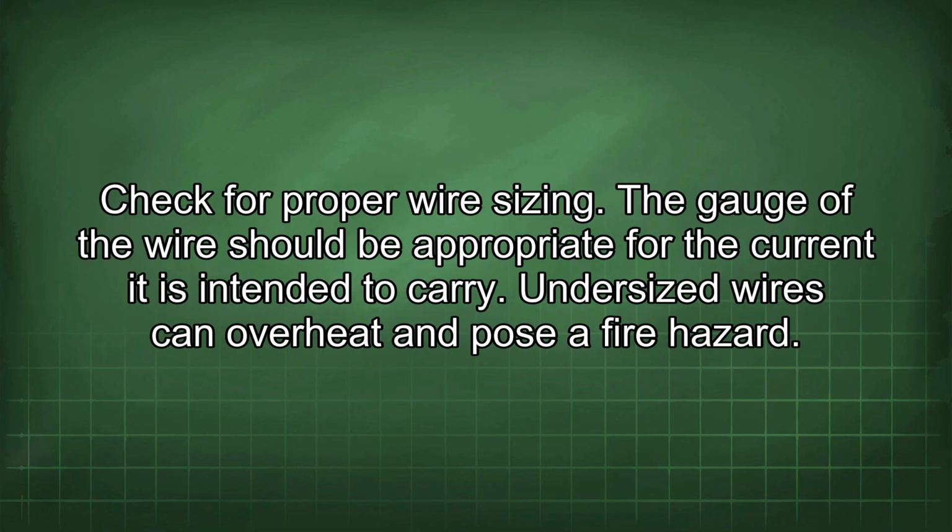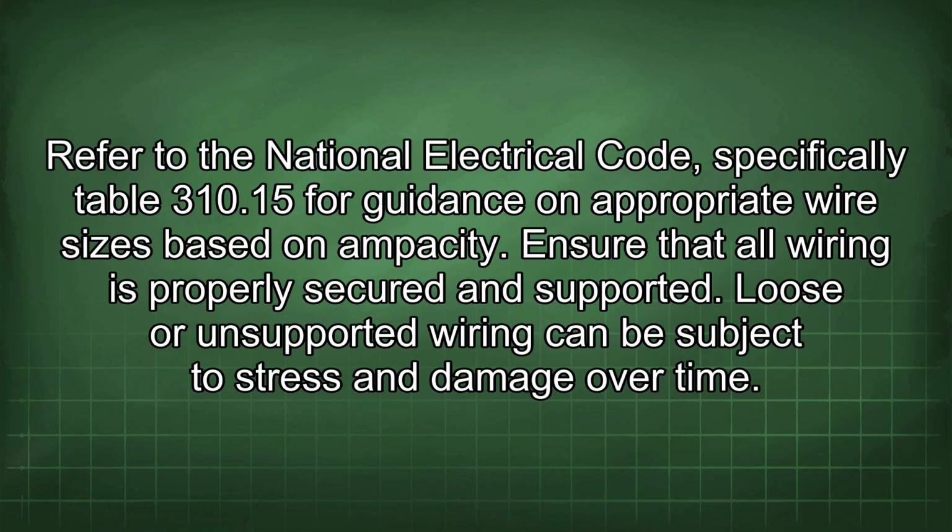Check for proper wire sizing. The gauge of the wire should be appropriate for the current it is intended to carry. Undersized wires can overheat and pose a fire hazard. Refer to the National Electrical Code, specifically Table 310.15 for guidance on appropriate wire sizes based on ampacity.